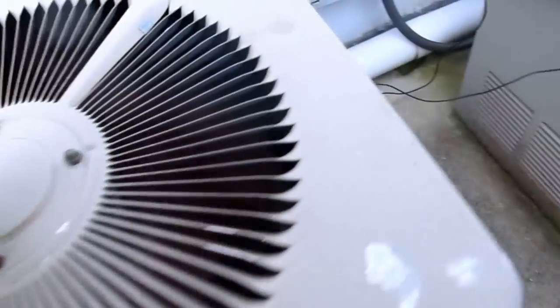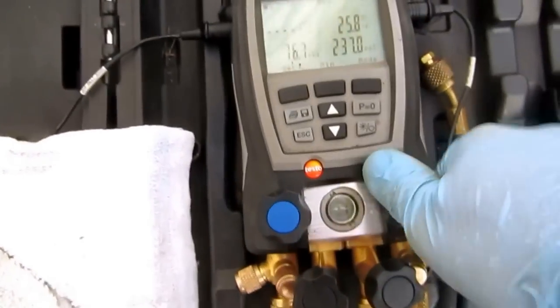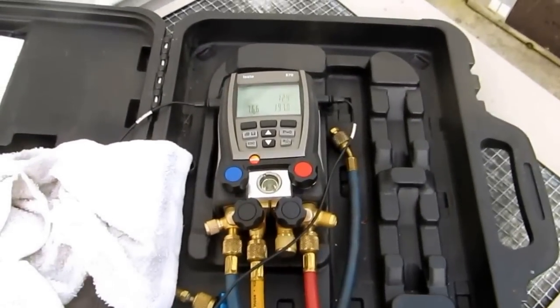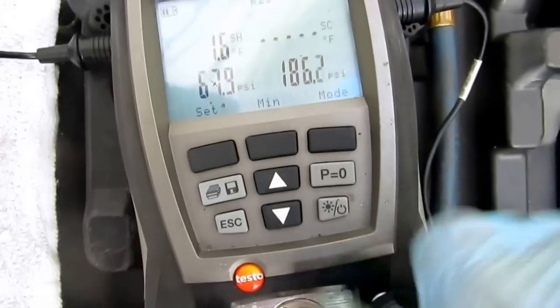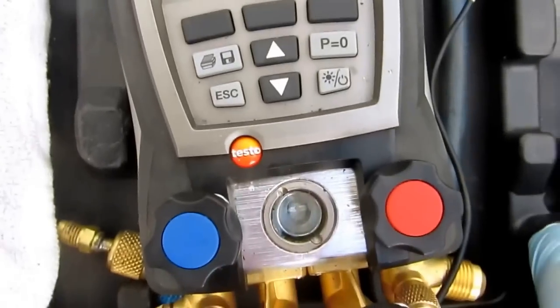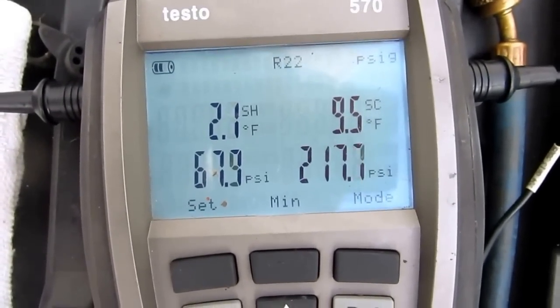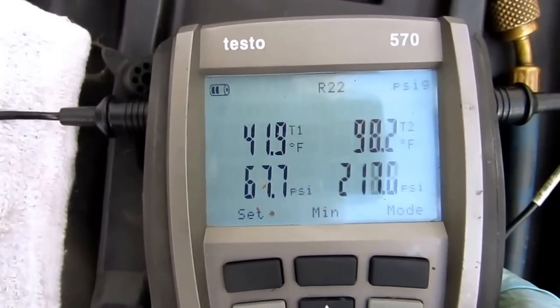You know that mold around there — any of that green mold? That's not right. Still flipping high, unbelievable. My subcooling's finally starting to come up, man. I dumped a bunch out. I don't believe how much I took out of this thing — unbelievable. Coming back like 38 on my suction line.